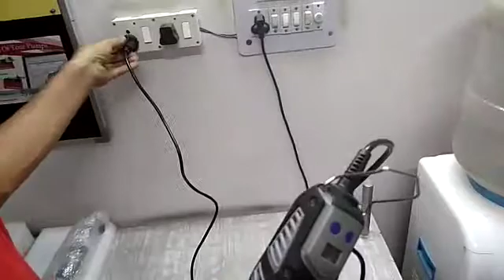Now you just have to slide the stator straight and tighten it on these small plastic threads. So your rotor and stator are assembled. Now we will go for the run. There is one on-off switch, 0 is off and 1 is on. So give the power. Once I give the power, this shows 8, meaning it will start from 8000. So never do a dry run.